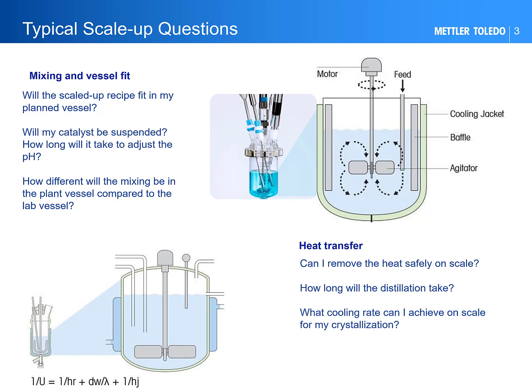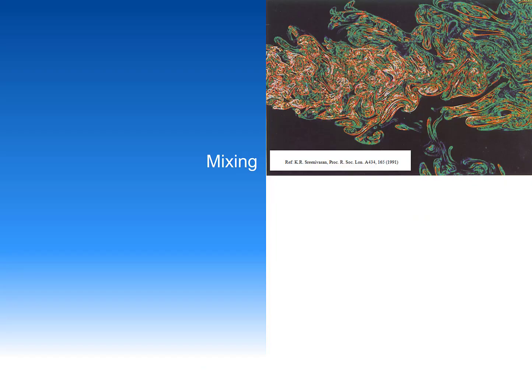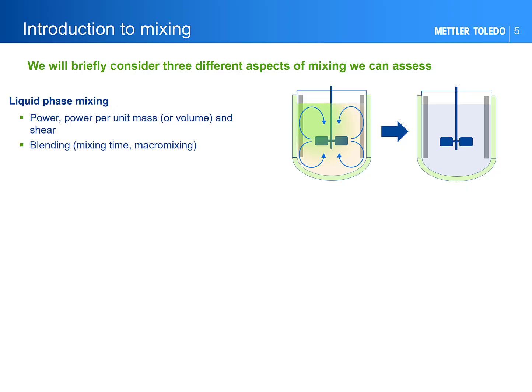In this talk I'm going to give an overview of the basic concepts in mixing and heat transfer with examples of how vessel assessments can be used when scaling from lab to plant. Starting with mixing — the picture here shows the complex nature of turbulent flow. When we talk about mixing we need to think about the phases — solids, liquids, gases — present in the vessel, as there are different mixing duties to consider. In a single liquid phase system we think about the amount of power being put into the liquid, the power per unit mass or volume, as well as blending.